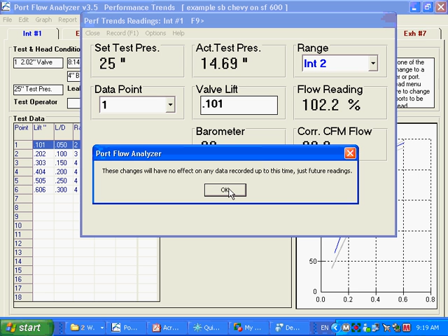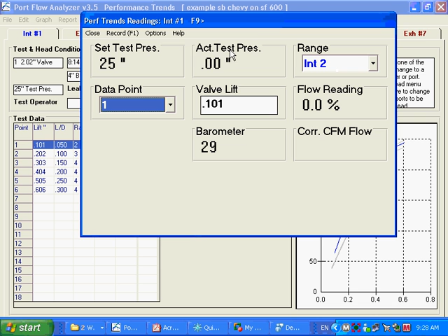Now you can see we're again flickering a little bit, which is a good sign. You want to see it changing a little bit - it's only a 100th of an inch. Now you can see we're getting flow readings here also, so those two are reading now. You can see here after we re-zero, the readings are reading 0.